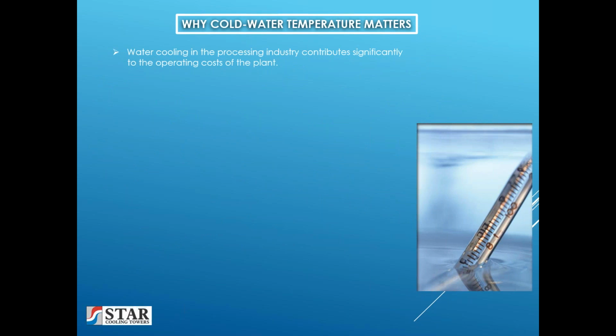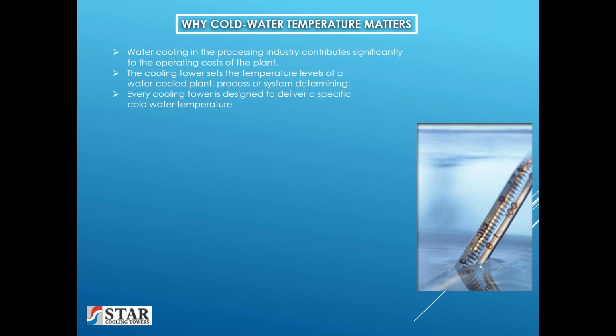So water cooling in the processing industry contributes significantly to the operating cost of the plant. The cooling tower sets the temperature levels of a water-cooled plant process or system, determining its production, energy utilization, and the profitability of the plant. Every cooling tower is designed to deliver a specific cold water temperature at a combination of wet bulb temperature, heat load, water flow rate, and airflow. This design cold water temperature would only be expected at the design conditions and only occur during the summer months.